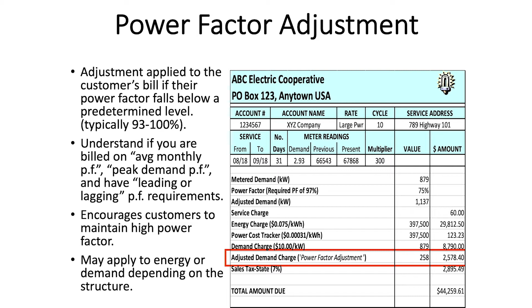So if I have a low power factor and I'm paying a big power factor adjustment, then the next step is I need to analyze if power factor correction capacitors are worthwhile and are a good cost-benefit ratio. In my example, and most of the Hoosier co-ops do it this way, we're going to have an adjusted demand charge. So there's the demand charge for the 879 kilowatts I was measured for my peak use. Then there's going to be a calculation that's going to add another 258 kW at the rate for another line item here. And we'll talk about that in a minute.